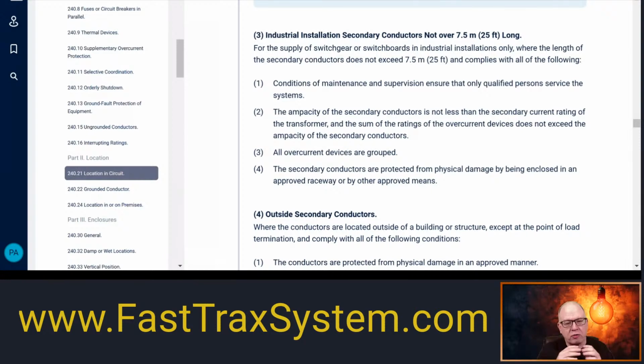But what you're going to do is, if you need to go longer, you just hit the disconnect within your 10-foot, meet your secondary rules, and then you can go from that 400 amp that's right there, and you can hit a panel and then go as long as you want. Again, within reason, of course.